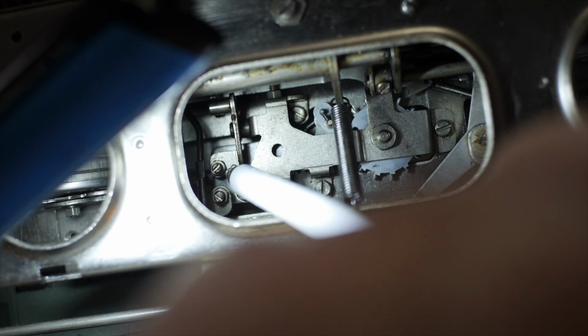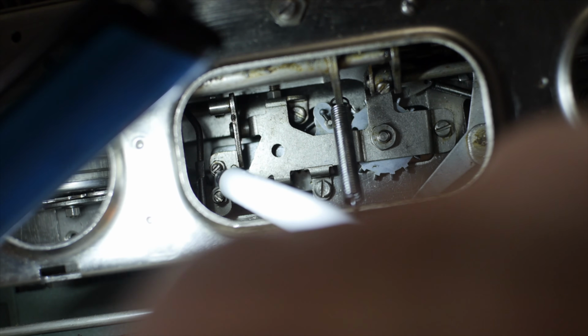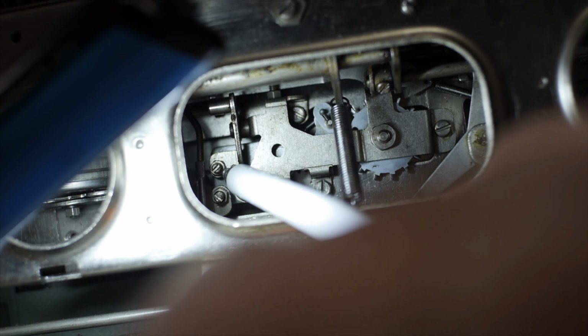You put a slotted screwdriver on the end of the screw to keep it from turning, loosen the nut, then adjust the screw - driving it in clockwise makes the tripping happen earlier, and screwing it out makes it happen later. I had to screw this one out to make it trip later because it was tripping too early. Then, keeping the screw from turning with a screwdriver, you lock down the nut.